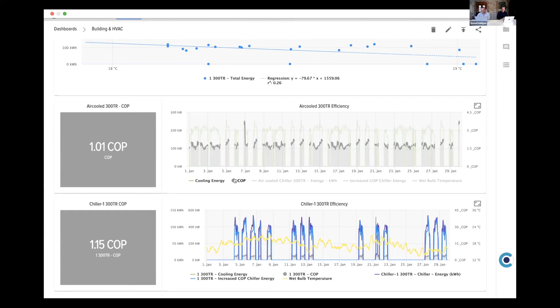From that cooling energy data point, we can now create an operating COP - a live COP, and COP relates to how efficient that piece of equipment is performing. So straight away, this guy was able to see a very low COP, not what he would have expected to see in an efficient system, with a lot of peaks and troughs there.